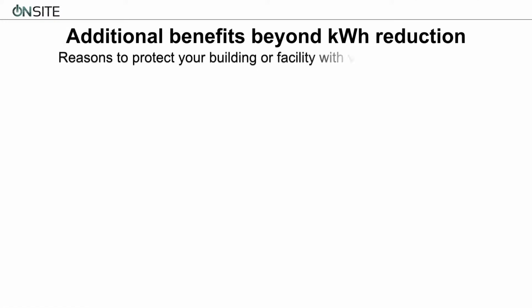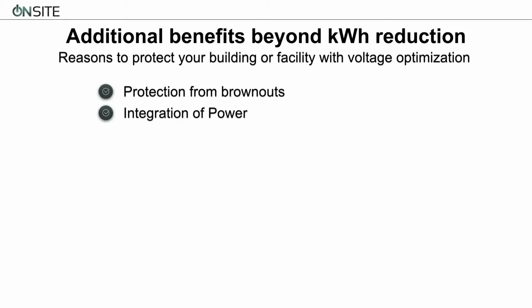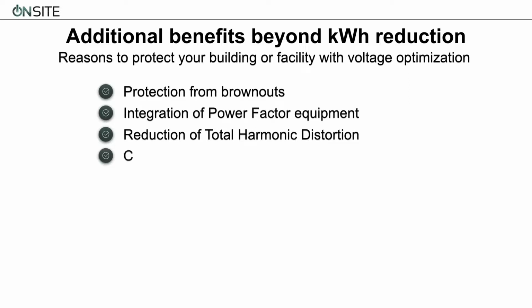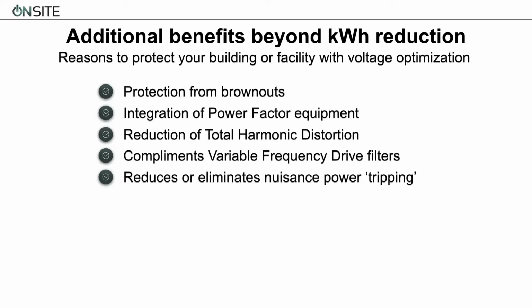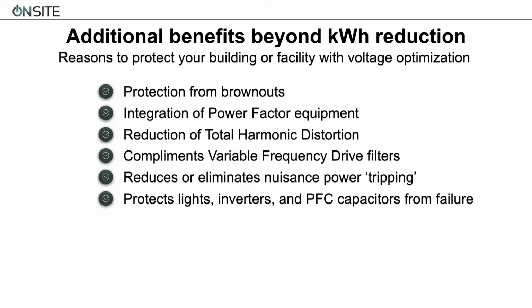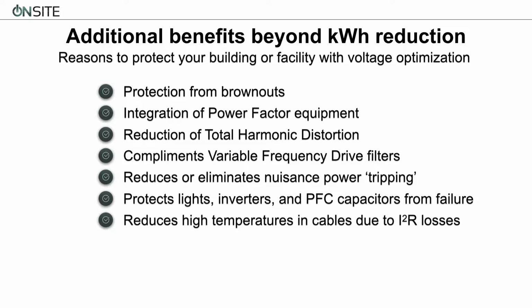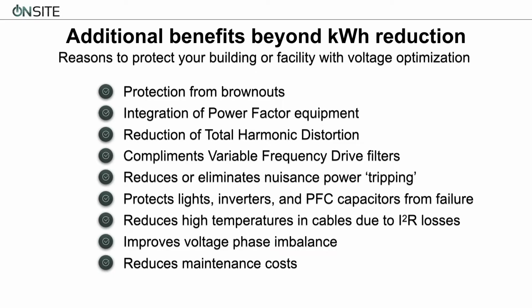Additional benefits of voltage optimization that go beyond kilowatt-hour reductions include getting protection from brownouts, the integration of power factor equipment, reducing total harmonic distortion, complementing variable frequency drive filters, reducing or even eliminating those nuisance power tripping effects, protection of lights, inverters, and power factor capacitors from failure, the reduction of high temperatures in cables due to resistance losses, the improvement of voltage phase imbalance, and the reduction of maintenance costs.